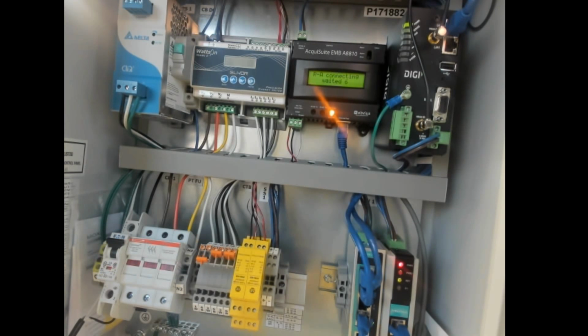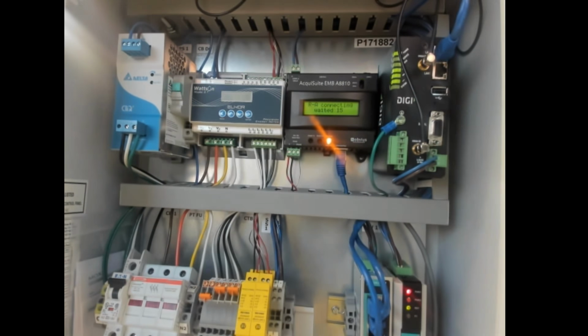I have a question about the deltas. Did I hear you correctly earlier that the quote-unquote high voltage will also accept 120 volt? No, it can accept down to 155, so it won't work off that. So even if you're pulling one hot leg and a neutral from a high voltage system like a 480, 277, you cannot use the low voltage option. It's got to be 120 volts AC.